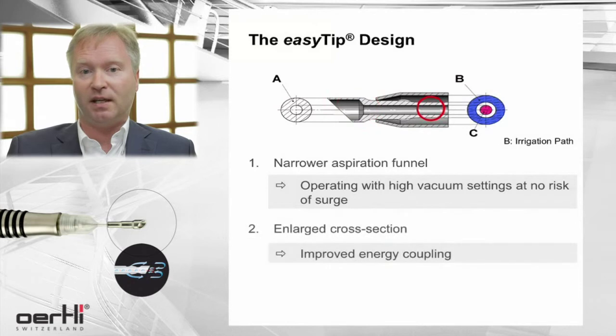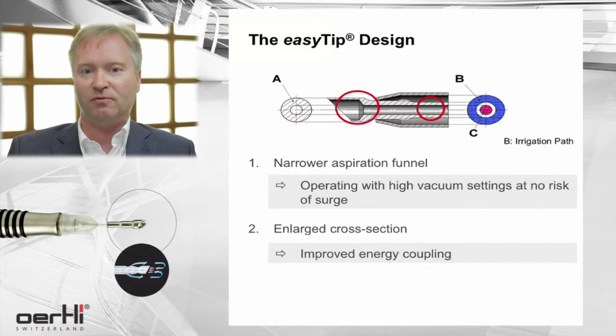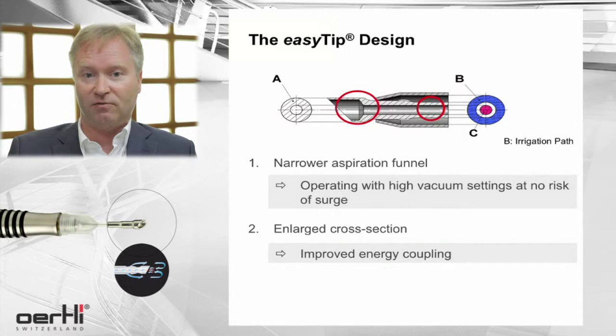The second change that has been made is at the mouth of the phaco tip — this has been enlarged. And the area that is responsible for phaco multiplication and energy coupling has been enlarged therefore.